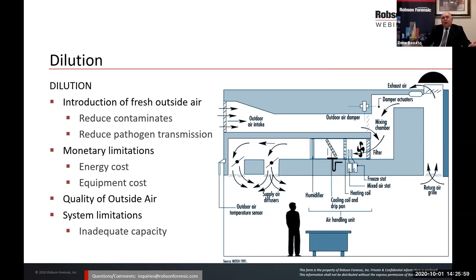Hospitals are designed that way. But you can't expect your typical building to be designed that way because it's cost prohibitive to bring in 100% outdoor air. And I've been belaboring that issue for a while. I'll keep going. The equipment cost is quite expensive as well. But the main limitation is that in a lot of these existing buildings, the equipment doesn't have the capacity to handle that additional outdoor air. It doesn't have the cooling capacity or the heating capacity to treat the additional outdoor air that's being brought in.